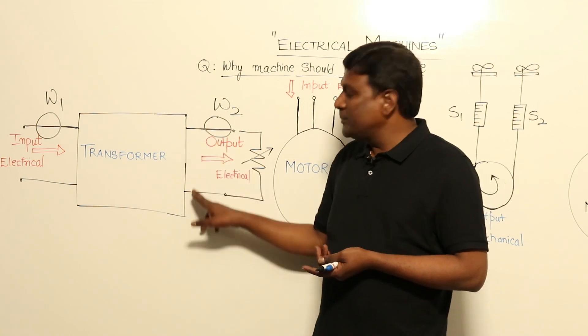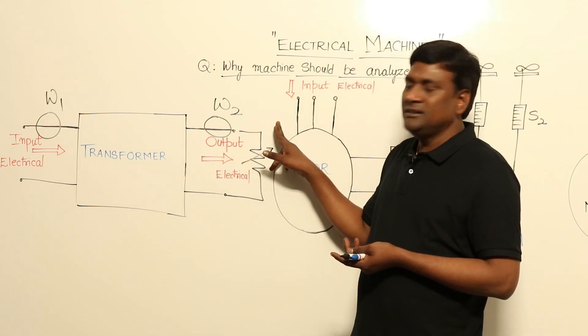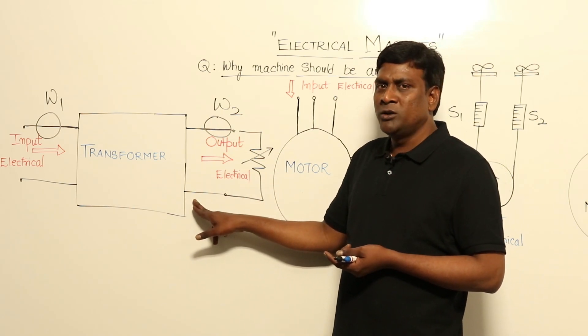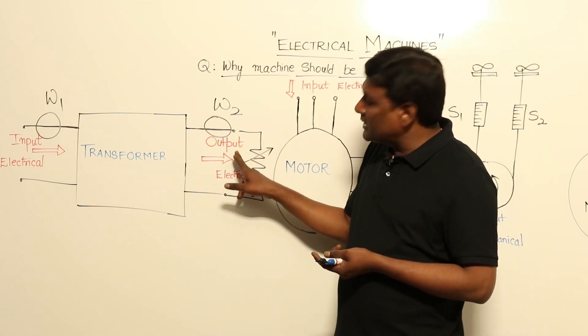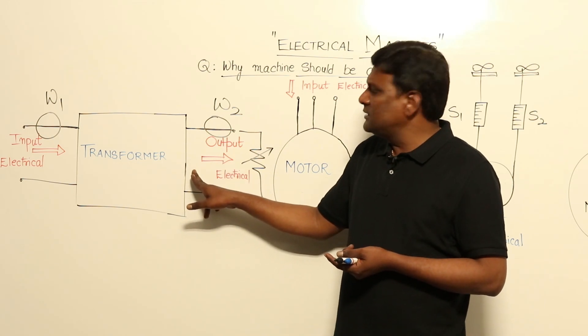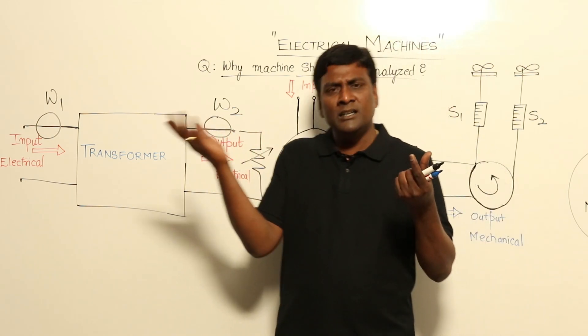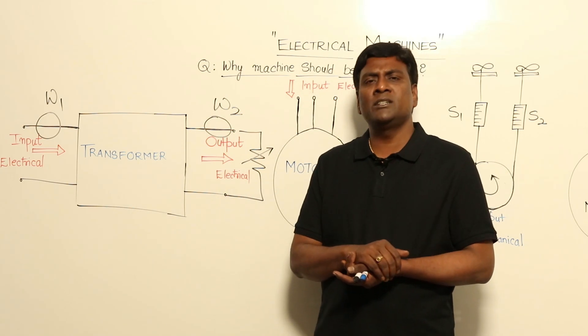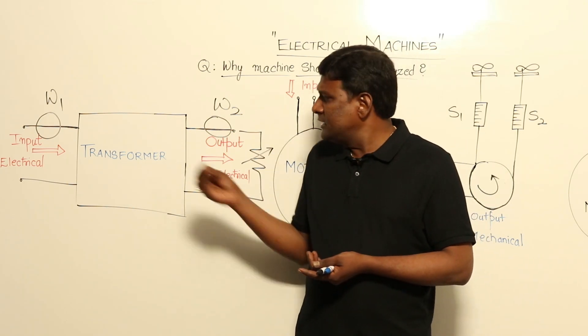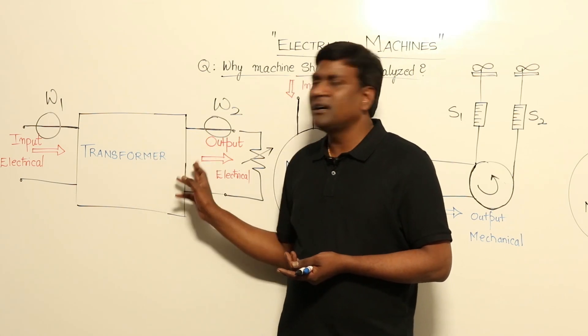Similarly, if I connect a voltmeter, first disconnect the load and take the no-load voltmeter reading, then reconnect the load and take the full-load voltmeter reading. That first voltmeter reading minus the second reading, divided by rated voltage, is nothing but voltage regulation. To find voltage regulation, I need not know what is happening inside the transformer — I can directly calculate it.